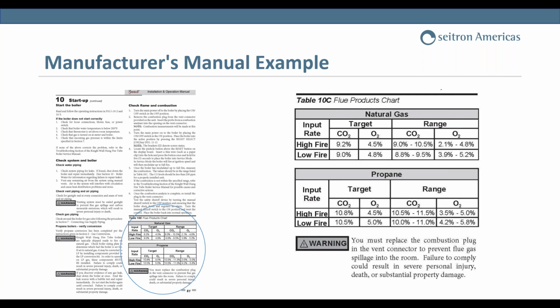In fact, as anybody here probably knows, if you've ever called tech support on a boiler or furnace, the first thing they're going to ask is what's your gas pressure, what's your O2, what's your CO2. They're going to ask where your analyzer is. It's very hard for them to detail things, especially on sealed combustion and high efficiency equipment. So analyzers are becoming a much more popular required tool instead of just an expensive luxury that only some guys have.